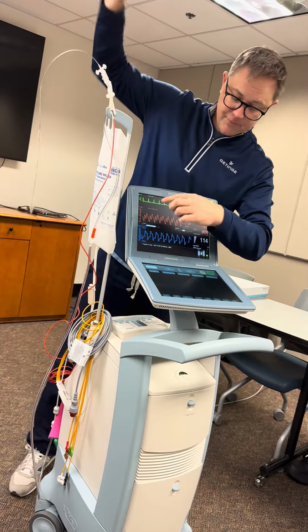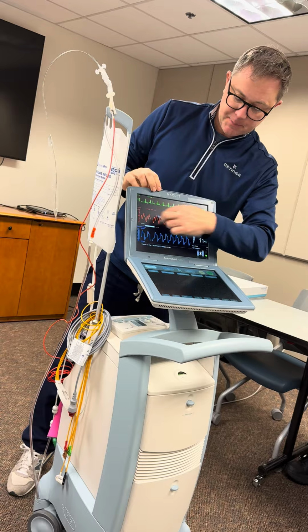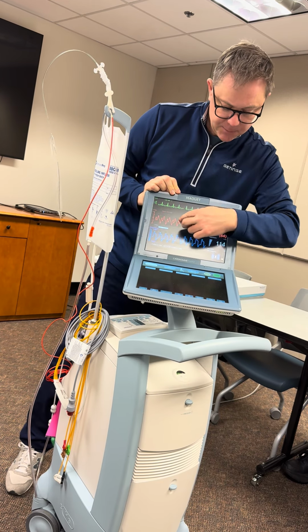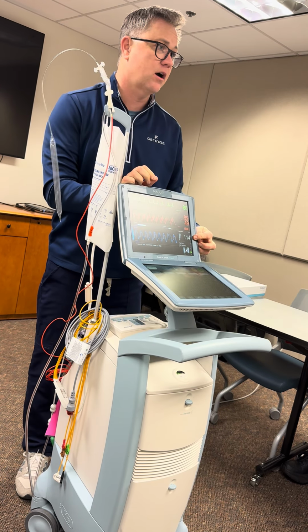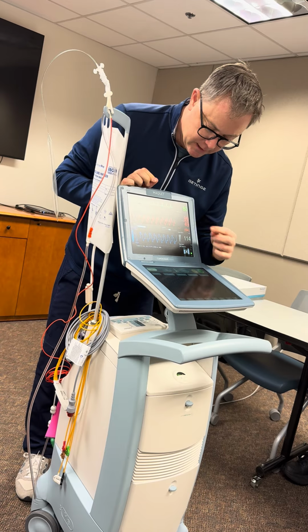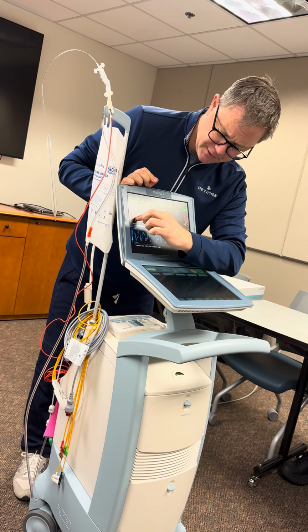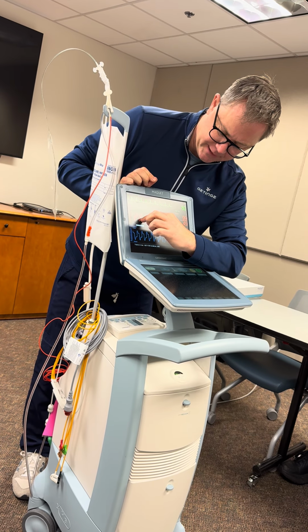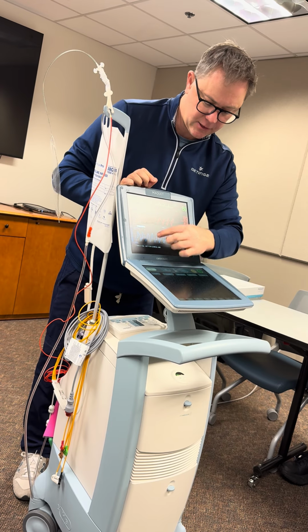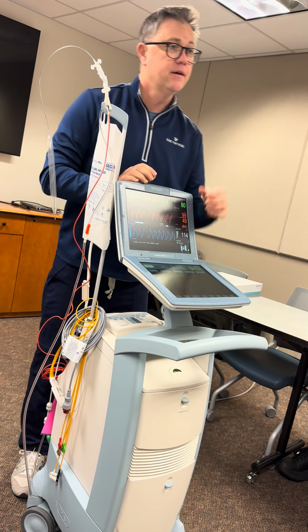So the Philips monitor is looking for the highest peak on this waveform, and the highest peak on this waveform is this diastolic augmentation, or this inflation pressure. So the balloon is inflating at the sharp V. Balloon inflates, and that's our diastolic augmentation pressure.